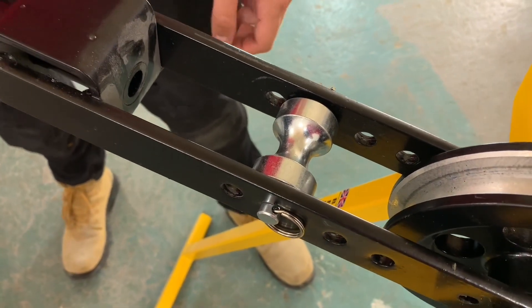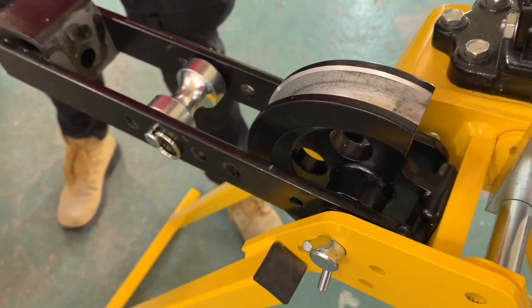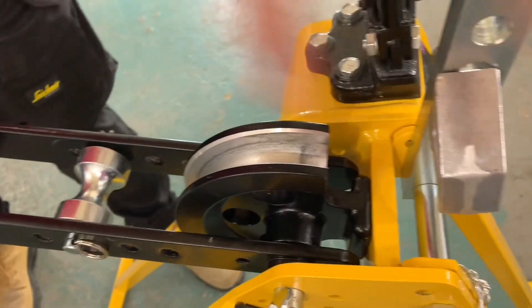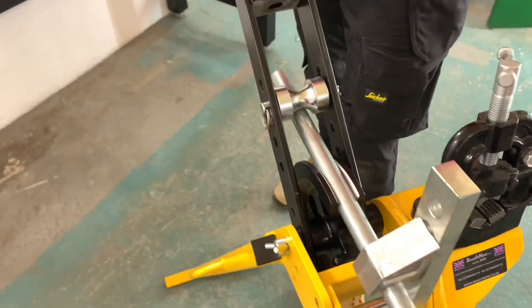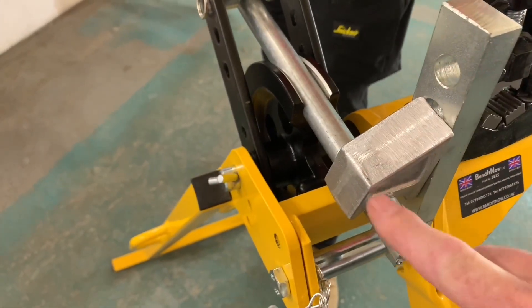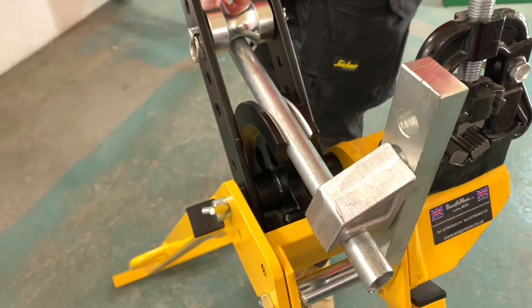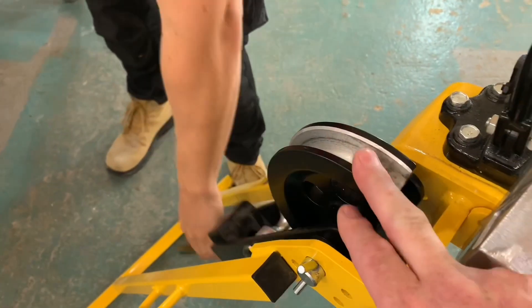20, 25, 32 for example. And this thing here — we would call this the former. This is a 20 mil former that we've got in at the moment. And this is the stop: it stops the conduit from flying up in the air. The reason there are several holes in there is that as the conduit gets larger — 20, 25, 32 — you can bring it up through the holes in the stop itself.